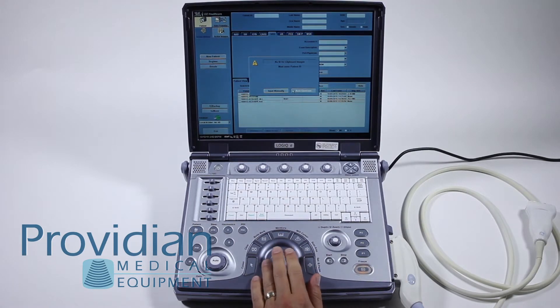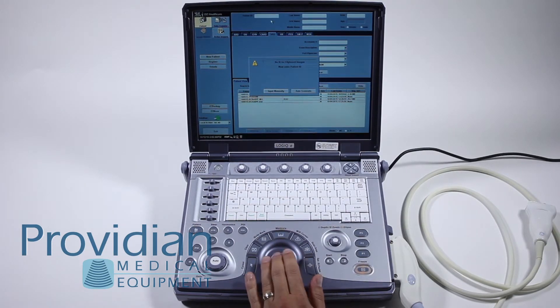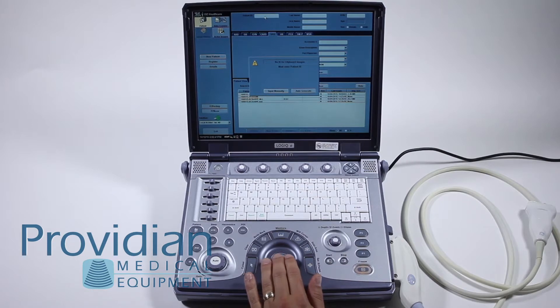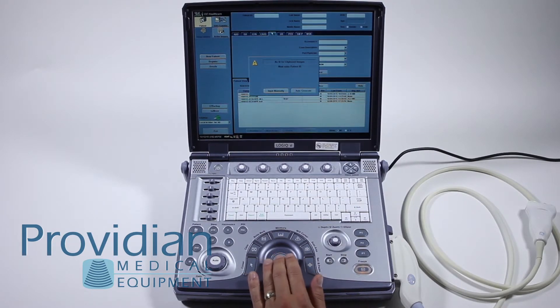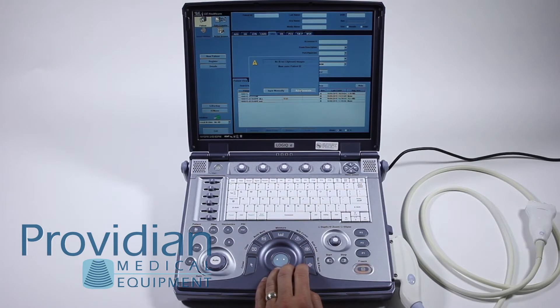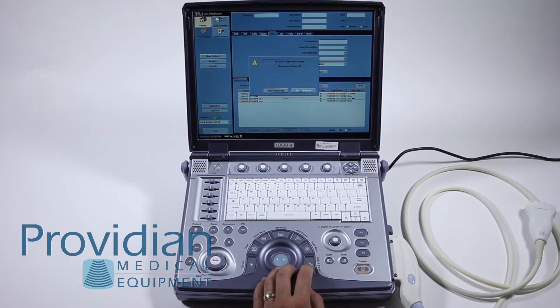We're going to click auto generate for the patient ID. Your machine may have automatically generated a patient ID for you. I've turned it off on this one because some machines will show up with it off, so I'll show you how to have it auto generate a patient ID. I think it's a good idea because it guarantees you will always have a unique patient ID for each patient. So right now I'm just going to say auto generate.